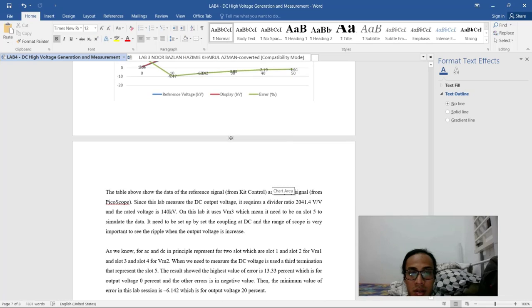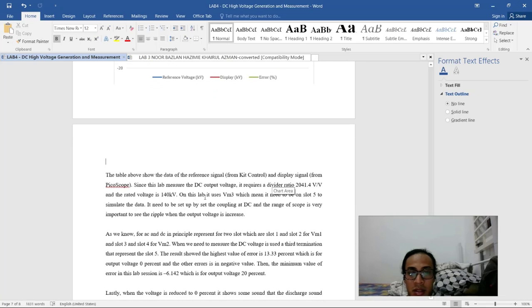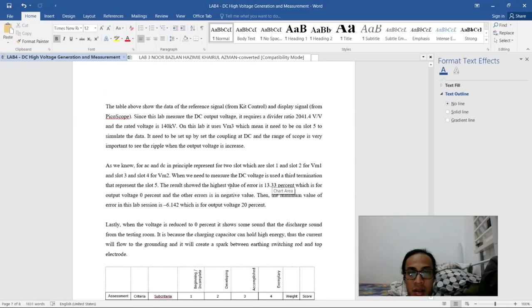Since this lab measures the DC output voltage, it requires a divider ratio of 2041.4, and the rated voltage is 140 kilovolts. This lab uses VM3, meaning we need to be on slot 5 to simulate the data, and we set it up by setting the coupling to the DC condition. The range of the scope is very important to see the ripple when the output voltage increases.